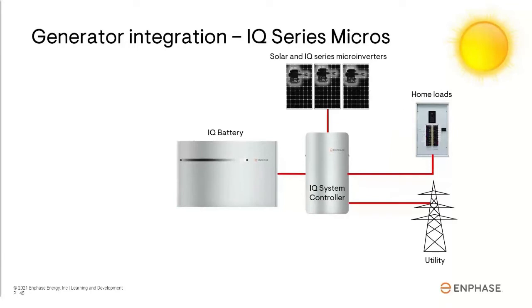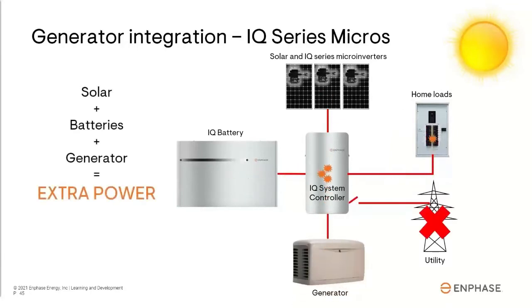Enphase generator integration eliminates the transfer switch. The generator is tied directly into the IQ system controller. During a grid outage, the generator, battery, and solar can all operate simultaneously. With all three power sources operating together during a grid outage, the home has the combined power to start and run large electrical loads. For example, a homeowner could run their AC or electric dryer only during the day when all three power sources are operating, and then conserve energy at night when running only off the battery.